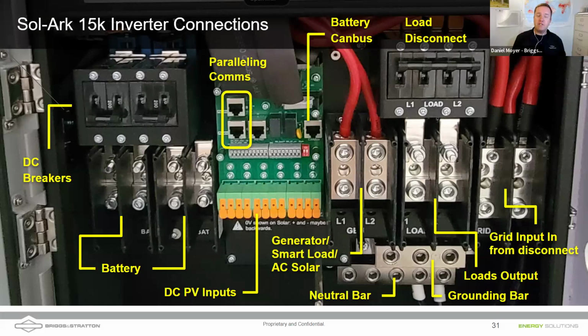We're looking at the inside of a Sol-Ark 15k here. A lot of people are familiar with this. We won't spend too much time here, but again, the 3 different ports: the grid port, which can pull in grid or a generator as well, the load output, and then the gen port. The gen port isn't just for generators; it can also be a smart load output, which I think is really key. We can also bring in AC coupled solar. We've got a load disconnect as well, and a battery CAN bus, where we plug in the communications down to the batteries.